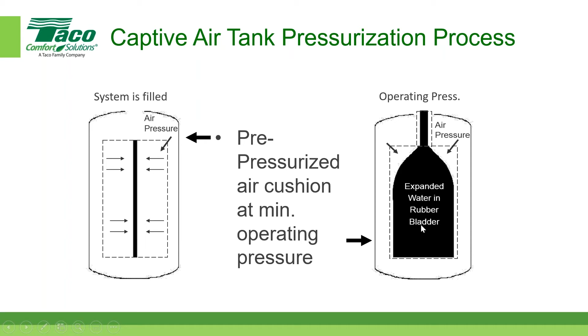I can't emphasize this enough: our technical staff at TACO, the Fall River folks, Rich and I—invariably once a month or whatever—we talk about the pre-charge, that pressurization the screen just showed. The pre-charge has to be properly set in the field. It has to be checked and properly set in the field.